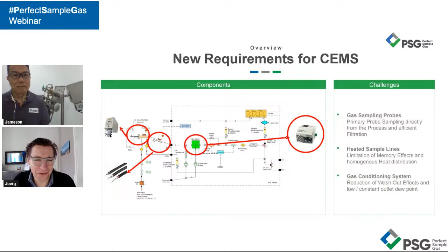When we start at the first point, Jameson, the gas sampling probe, the primary gas sampling. I mean, we often say our components in general are underestimated, but I think the probe is one of the components where people think, okay, it's just a filtration. And if I do something wrong in the primary probe sampling, it's not a big issue. I will probably just need to change the filter more often. But I think this is so wrong, right?